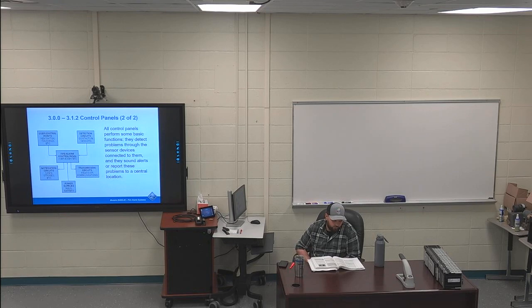3.1.2, Fire alarm control panel listings. So that's what's going to be approved to be a fire alarm panel. Second sentence is highlighted. Common UL listings, Underwriters Laboratories listings, for fire alarm control panels are UL 864 for the fire alarm control panel and UL 985 for the household fire warning system unit. So your equipment has to be rated by Underwriters Laboratories or some type of listing saying this is good equipment to use.